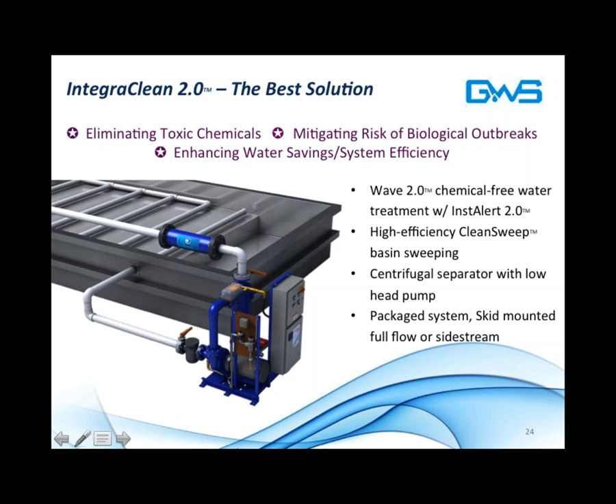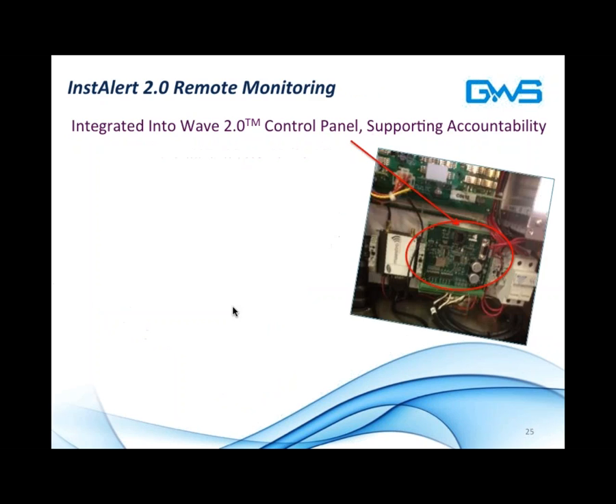The first is the Wave, which is the non-chemical electrodynamic frequency water treatment system that controls scale, biological growth, and corrosion, and controls conditions within the tower to promote low corrosion. It includes a high-efficiency clean sweep basin system, which requires half as much energy as traditional basin sweeping systems. A centrifugal separator is used to capture sediment from the tower and promote very low biological counts within the system. And this is all done in a package system which incorporates remote monitoring. So I'd like to switch gears just briefly here before we conclude and talk a little bit about what that remote monitoring does when it's coupled with this type of equipment.